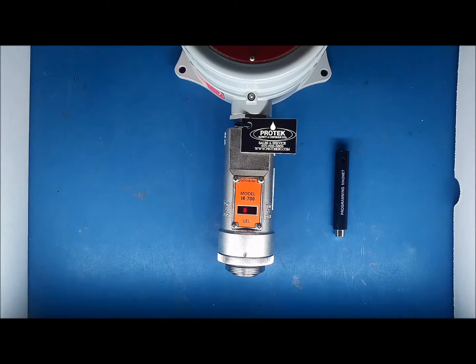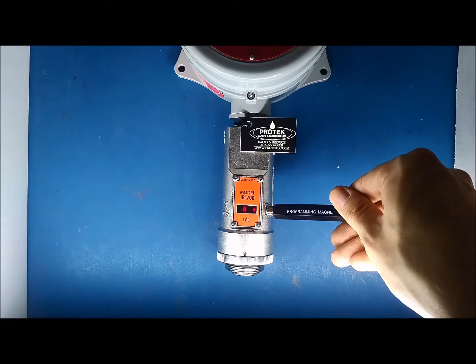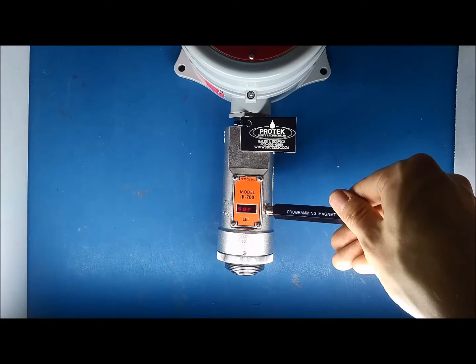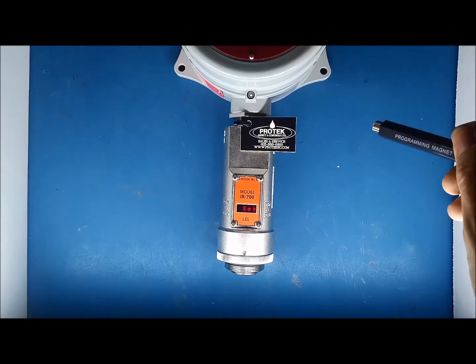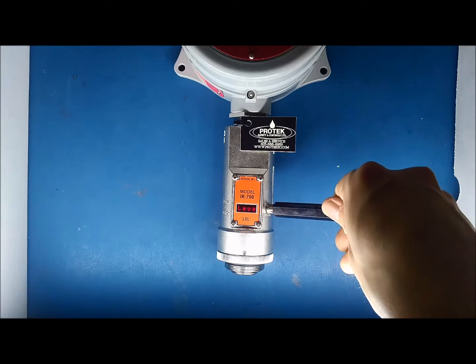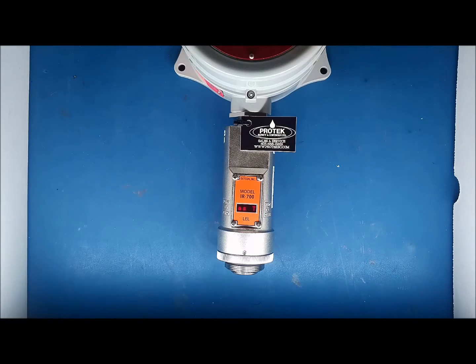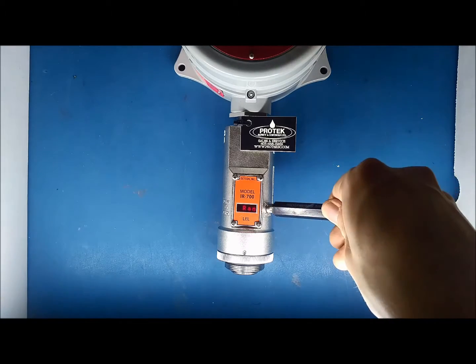With the unit powered up, hold the Detcon programming magnet over PGM-2 for 5 seconds. The display will read View Sensor Status across the screen. Hold the magnet over PGM-2 until an arrow pointing right appears, then immediately remove the magnet. The display will now read Set Auto Span Level.